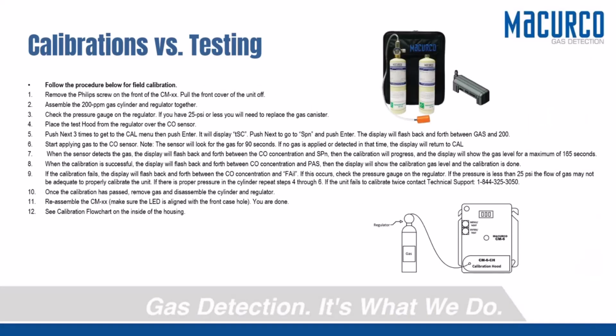Keep going on the same topic. In our manual, it shows the exact process of calibration. This is basically cut and pasted out of the manual. What I want to show you here is how simple it actually is. So what we've done is if you eliminate 1, 2, 3, and 4 off of this, it's basically just saying, hey, here's how you prep your detector, take the screw out, take the hood off, etc. Number 5, 6, 7, and 8 is really the process. 5 is where you start to get to the cal menu.